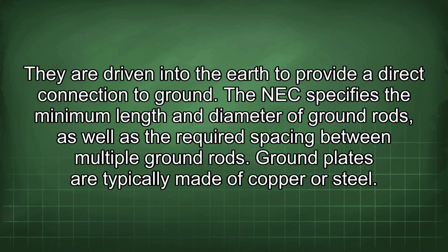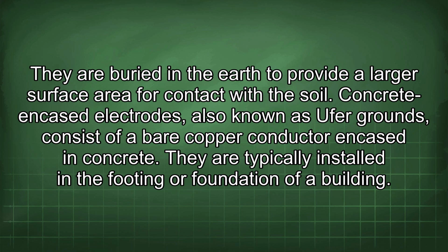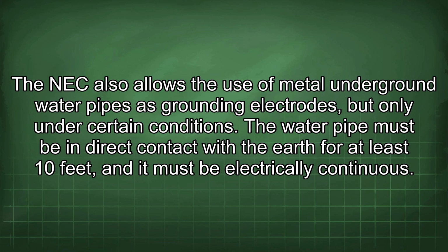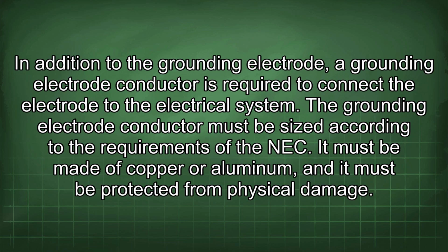The NEC specifies the minimum length and diameter of ground rods, as well as the required spacing between multiple ground rods. Ground plates are typically made of copper or steel. They are buried in the earth to provide a larger surface area for contact with the soil. Concrete encased electrodes, also known as Ufer grounds, consist of a bare copper conductor encased in concrete. They are typically installed in the footing or foundation of a building. The NEC also allows the use of metal underground water pipes as grounding electrodes, but only under certain conditions. The water pipe must be in direct contact with the earth for at least 10 feet, and it must be electrically continuous.